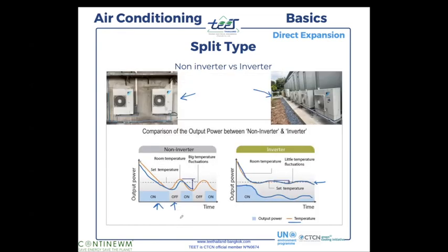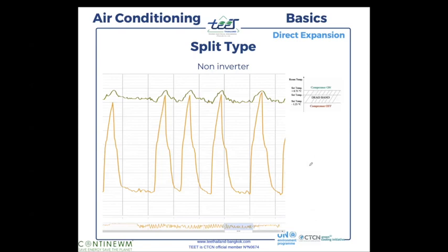So we know, in a non-inverter, we save on average 25%. On an inverter, we save 15 to 20%, okay? In normal conditions, all right? So this is important to know when you make your proof of concept, projection of savings and ROI calculation, to know this in advance before even starting the proof of concept. So they have a figure of what would be the ROI and payback of their system based on the technology they use, okay?